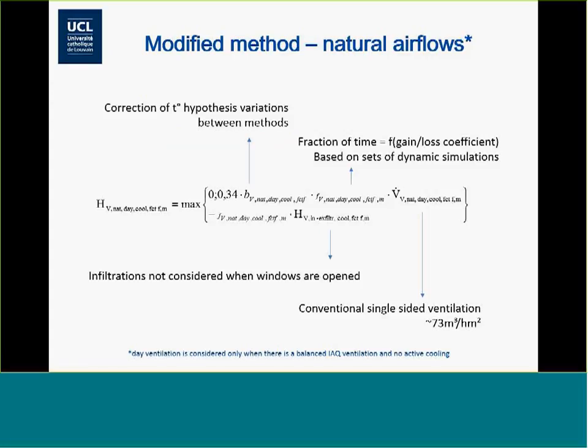To go a little bit deeper in the way we will calculate airflows and ventilative cooling, we have in that term, which is dedicated to natural ventilation at daytime, so intensive natural ventilation, not IAQ, a calculation which is based on a conventional airflow, which is around 73 cubic meters per square meter and per hour. This is an estimation of what we can have with a medium temperature difference between inside and outside for a single side ventilation and a window-shaped opening. So this is a conventional value. You cannot change that in your design. So there's no way right now to take into consideration cross ventilation, for example. That's not yet included because of the uncertainty of pressure coefficients on the building. We do not have something which is quite consistent enough to go to regulation at that time.